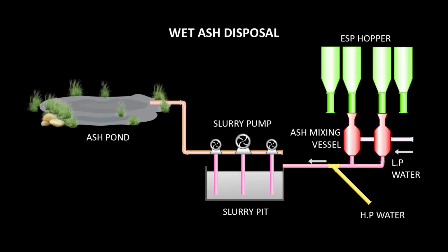Ash handling system. Wet ash disposal. The fly ash carried by the flue gas is collected in the electrostatic precipitator. It is mixed with low pressure water in the ash mixing vessel to form slurry. The slurry is moved to slurry pit by high pressure water jet. Then the slurry is pumped to the ash pond by ash slurry pumps.